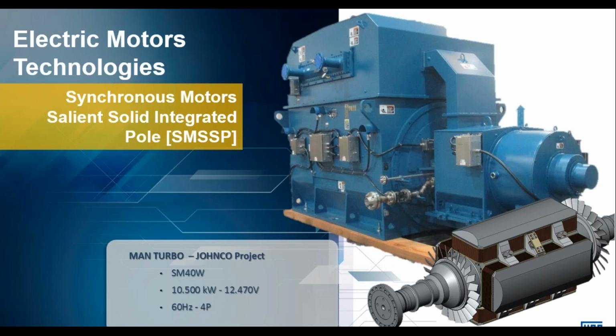Then we move on to a salient pole design, but this one has a solid integrated pole. This is a very expensive machine. If you look at the picture, this rotor is essentially machined out of a single solid block of steel, both the shaft and the pole shoe. And so you can imagine the price of this machine.